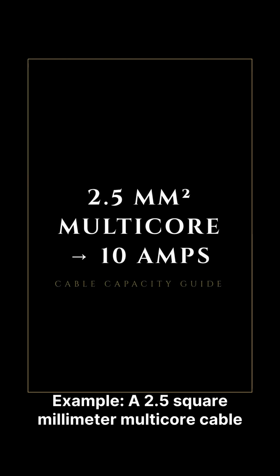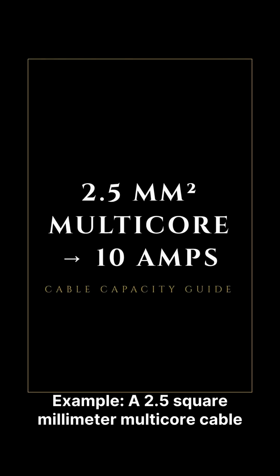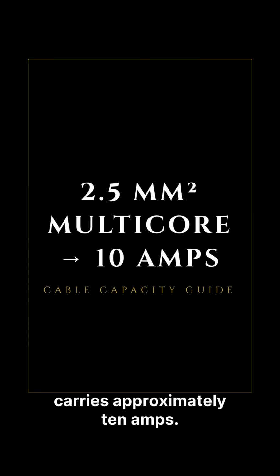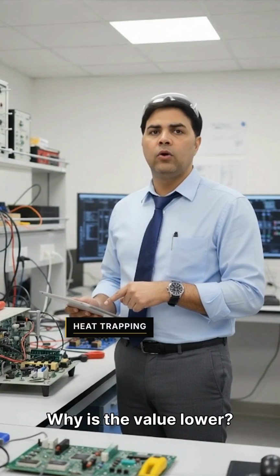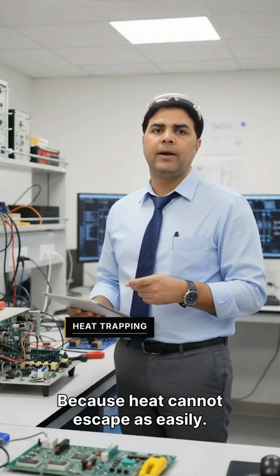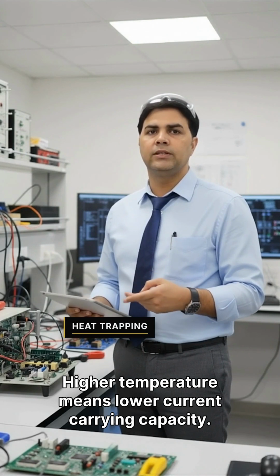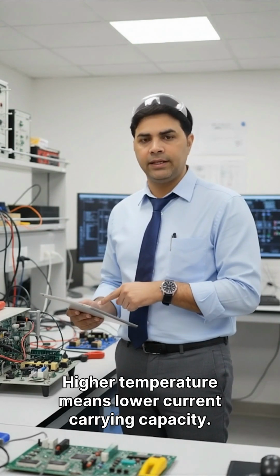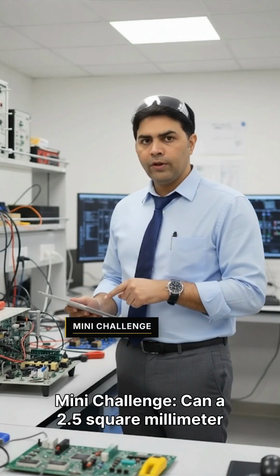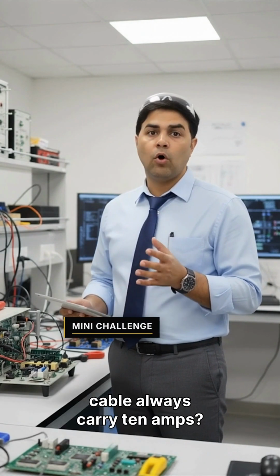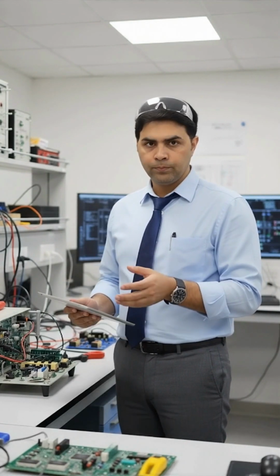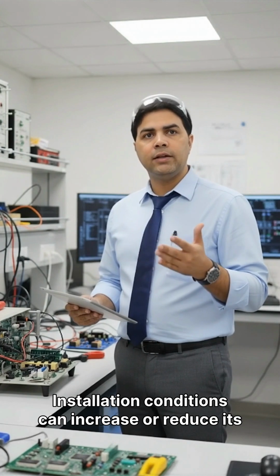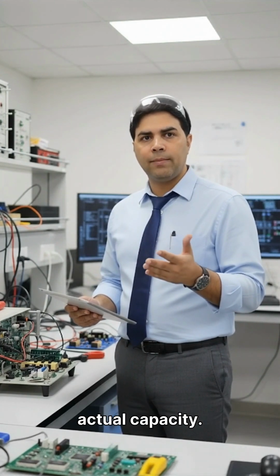Example: a 2.5 square millimeter multi-core cable carries approximately 10 amps. Why is the value lower? Because heat cannot escape as easily. Higher temperature means lower current carrying capacity. Mini challenge: can a 2.5 square millimeter cable always carry 10 amps? No. Installation conditions can increase or reduce its actual capacity.